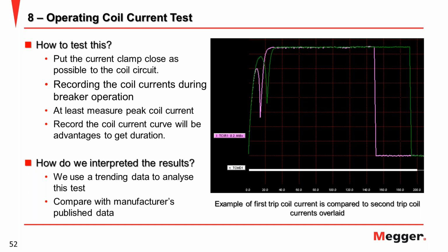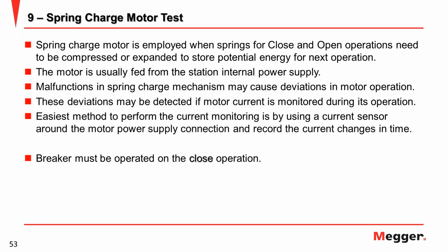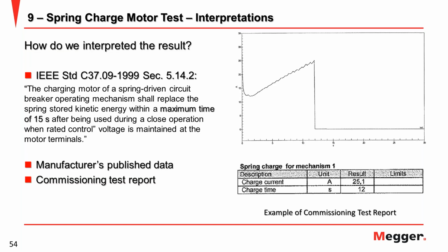Yeah, we need to use the trending data to analyze this test. Spring charge motor test is, as I know, something some OEMs put on the basic test list because they want to know the time of the charging process. Based on the C37 standard, the maximum time should be less than 15 seconds. So you need to do an adjustment if you get a spring charging motor time of more than 15 seconds.